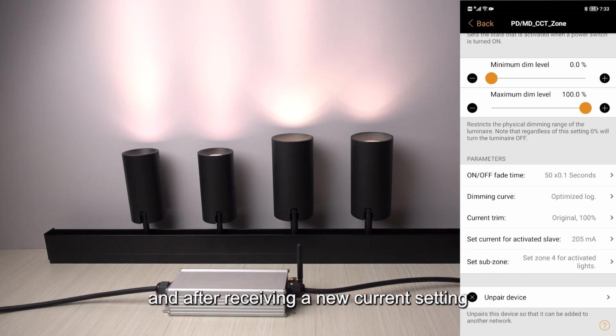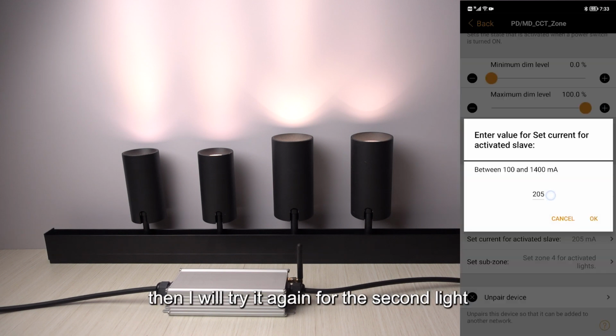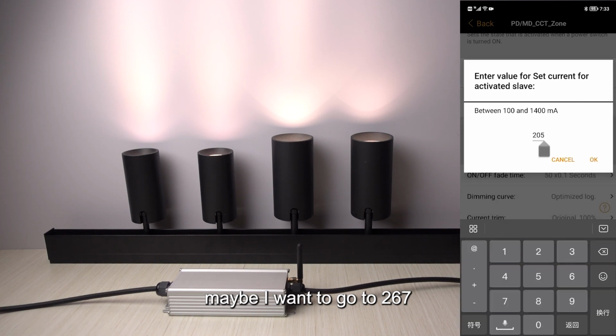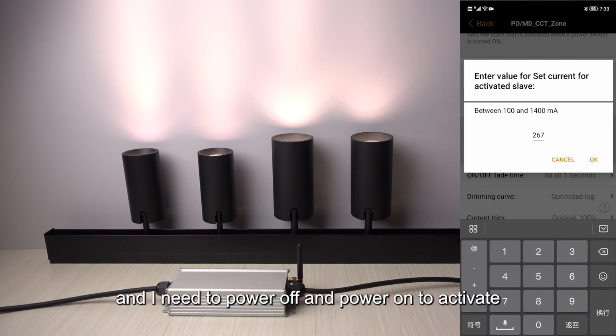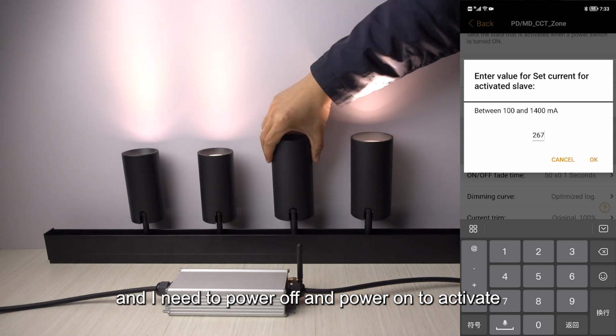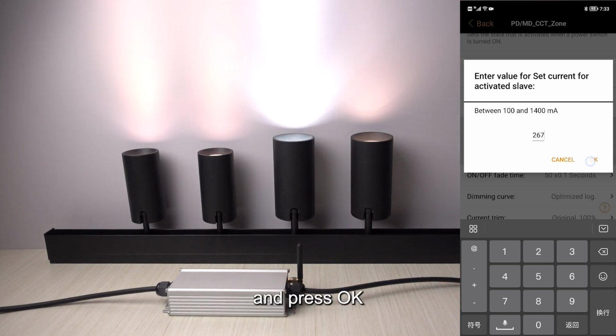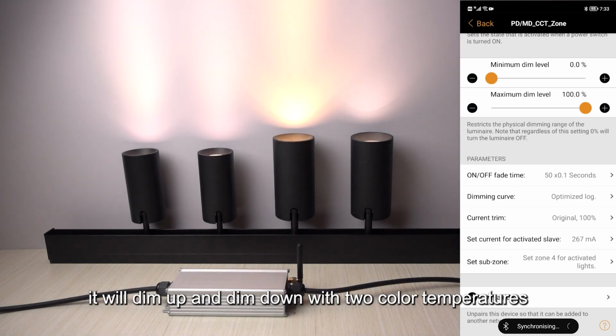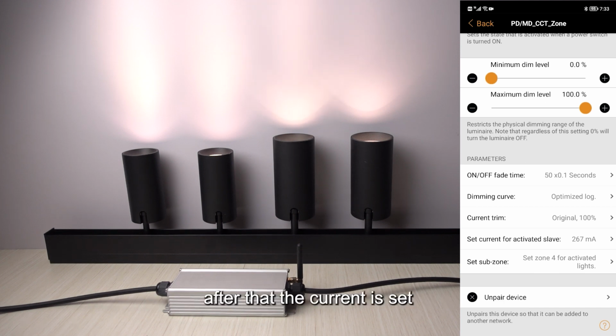And after receiving a new current setting, the slave driver will adjust the light on and off and brightness high and low, adapting to the lighting fixture to make a full-time DC dimming. So this is normal. And I will try it again for the second light. Maybe I want to go to 267 and need to power off and power on to activate and press OK. It will dim up and dim down with 2 color temperatures, and then after that the current is set.